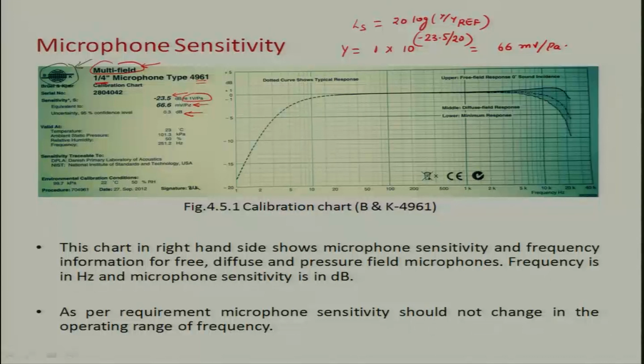They made all these measurements at 23 degrees centigrade, when the static pressure was 101.3 kilopascals and humidity was 50%, and they made this calibration by checking the microphone at 251.2 hertz.